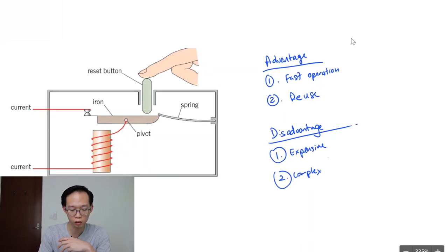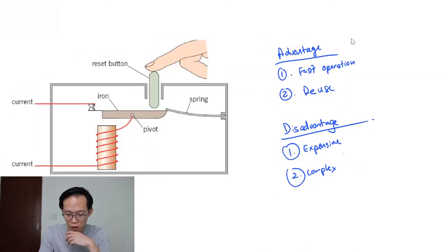So the advantages for a circuit breaker are that number one, it is a very fast operation. Now a fuse takes time to heat up and blow, whereas for a circuit breaker, the magnetic attraction happens instantaneously, almost instantaneously. And so it cuts the current much faster than a fuse. So that's the first advantage.